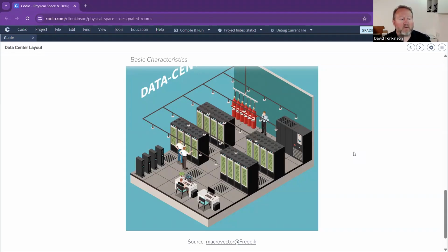But remember, if you have a data center where you have data aisles with your racks that are covered in essentially polystyrene, to allow you to have a cold aisle and a hot aisle, a lot of air conditioning systems will allow you simply to blow air into one location rather than into 2. So if you have another aisle that is unused, you will be able to not blow air into that particular aisle. And that then makes your air conditioning more efficient. You're only cooling the stuff that needs cooling rather than stuff that's empty. They're not blanking walls.